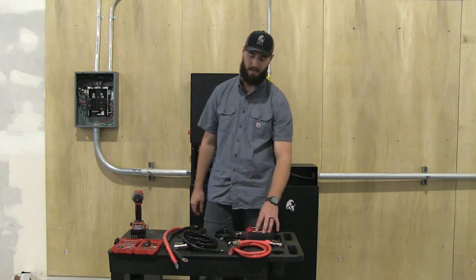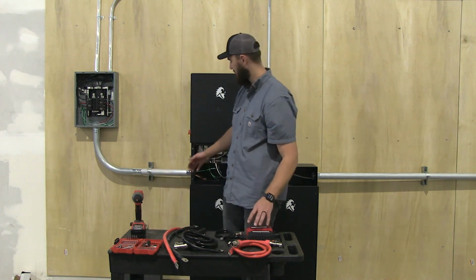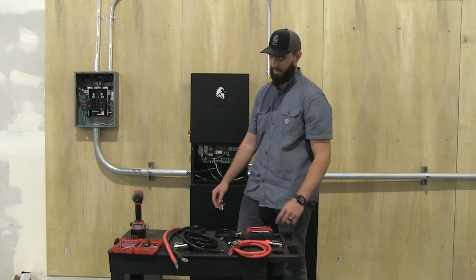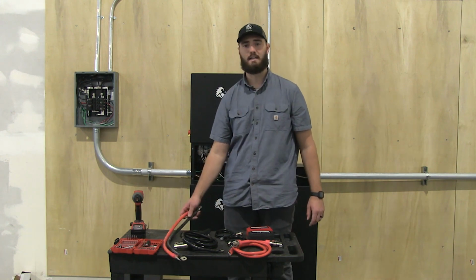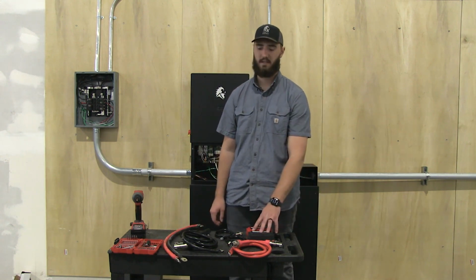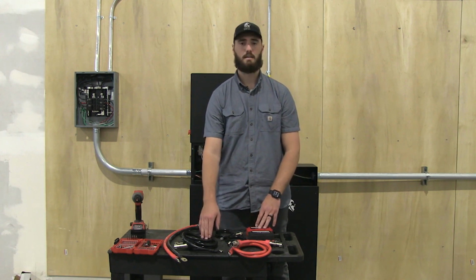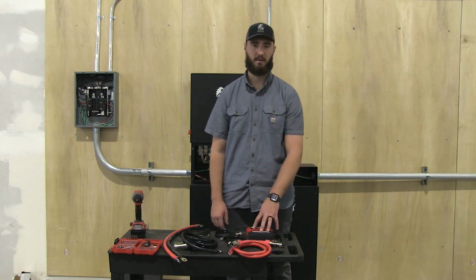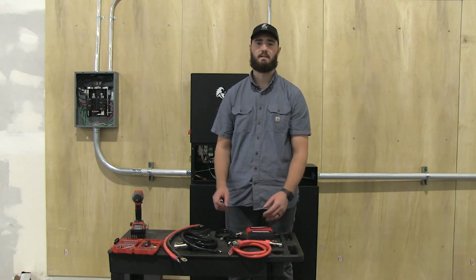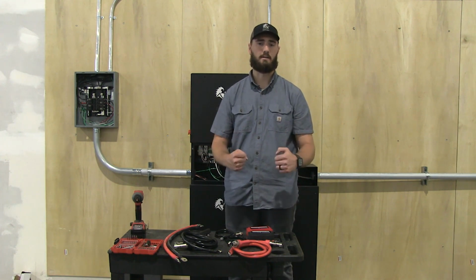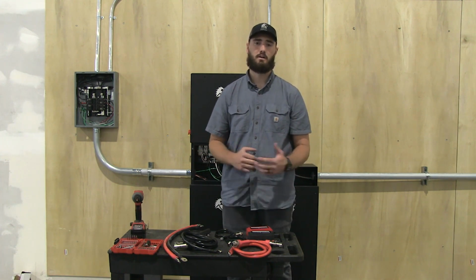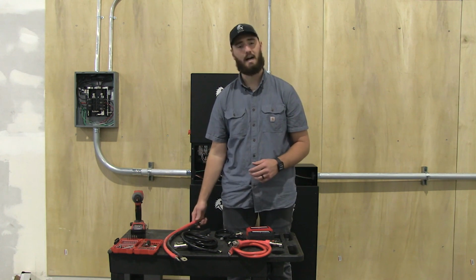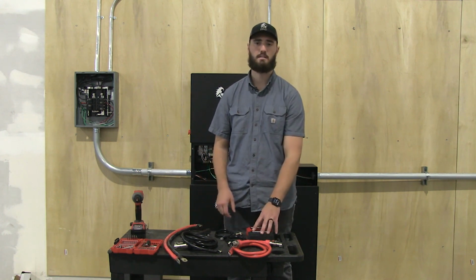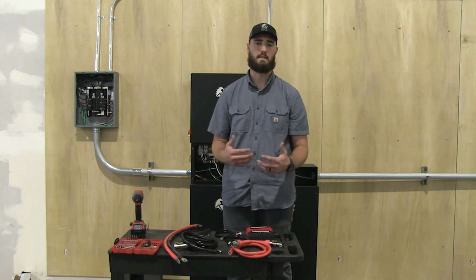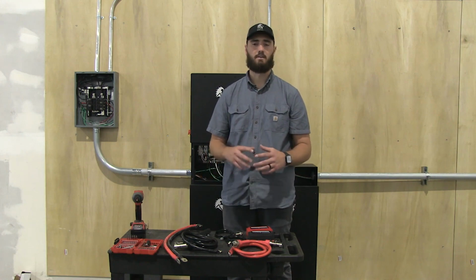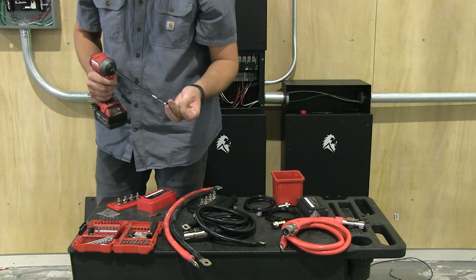Let's start by mounting our bus bars beneath the inverter, connecting our eyelet to eyelet cable to the bus bars, connecting the battery cables to the bus bars, and then finally connecting the cables to the batteries. This ensures that when connecting the eyelets to the bus bars, there is no voltage present on the cables until everything has been installed.